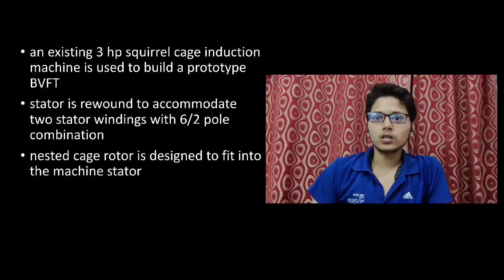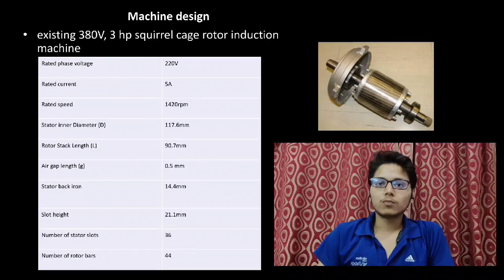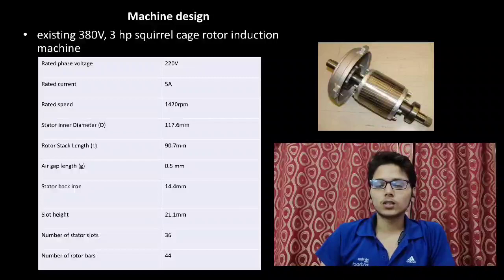A nested cage rotor is designed to fit into the machine stator. Machine design: the prototype machine will be constructed using an existing 380 volt, 3 horsepower squirrel cage induction machine. The design is restricted by the stator dimensions given in this table. The stator is rewound to house two stator windings with dissimilar pole numbers P1 and P2. The suggested numbers of poles are 6 and 2. A nested cage will be built with the same diameter as the old rotor. All the dimensions of this induction machine are given in this table.